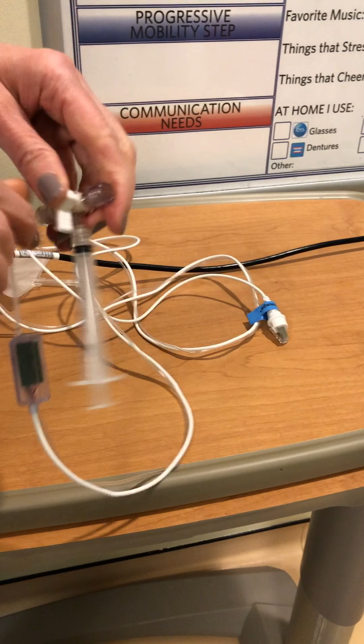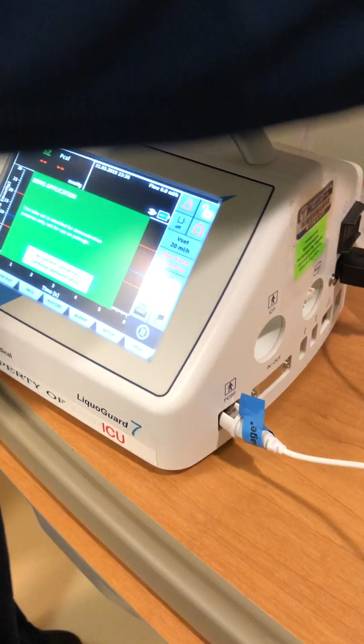So this piece of equipment is called the Liquoguard. This is what the neurosurgeon will use for diagnosing NPH, normal pressure hydrocephalus. A lumbar catheter will be placed in the patient's lumbar region in the OR by the neurosurgeon, and when they arrive to the unit, you're going to get this pump, and the tubing that comes with the pump looks like this.